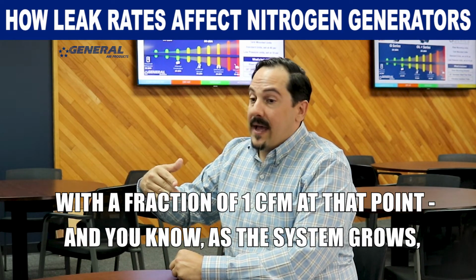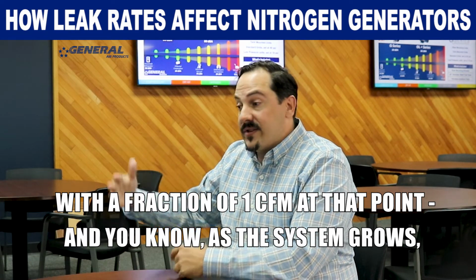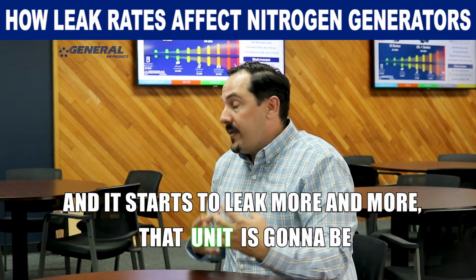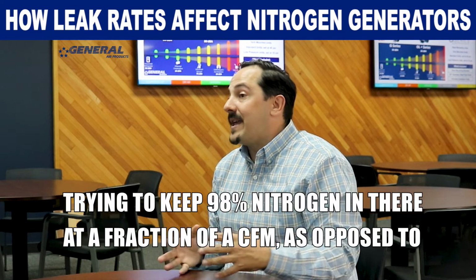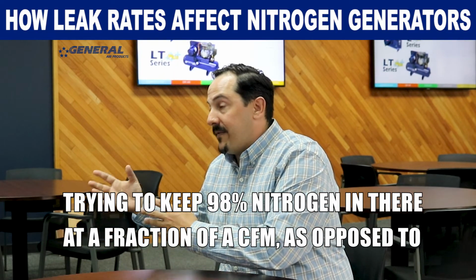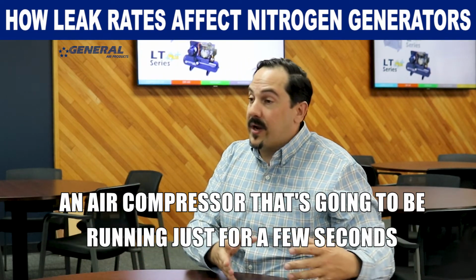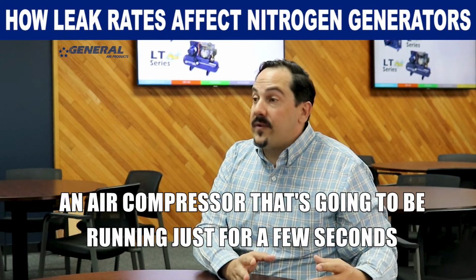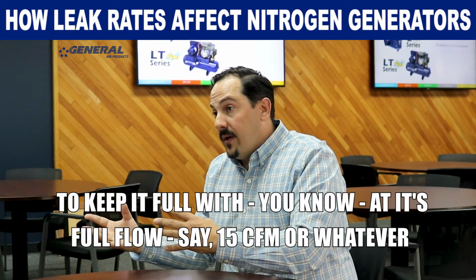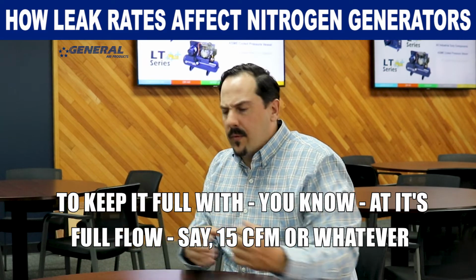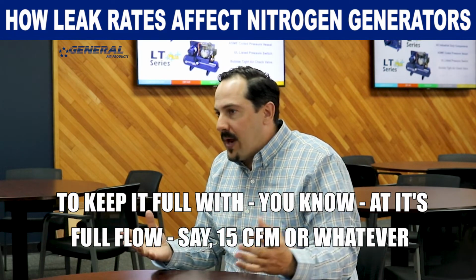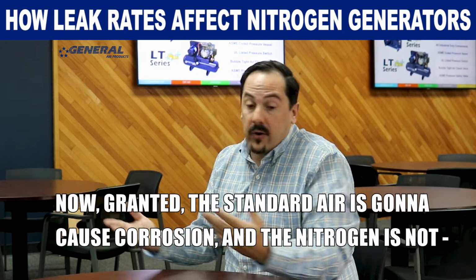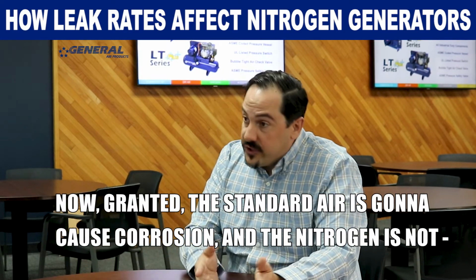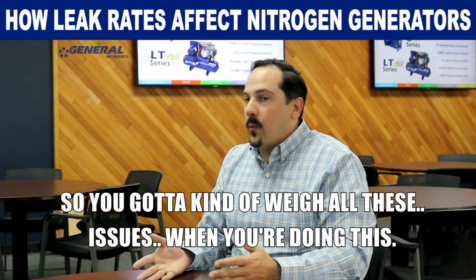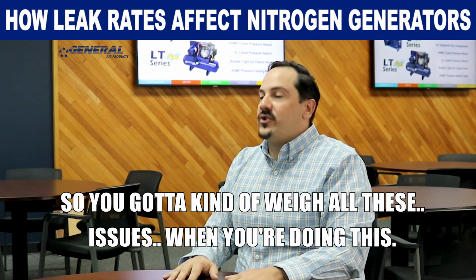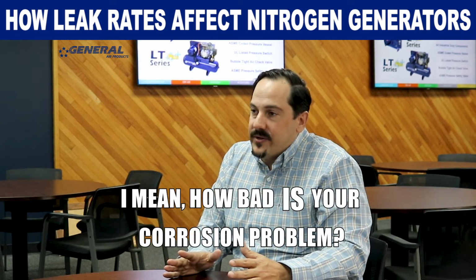and you're dealing with a fraction of 1 CFM at that point. As the system grows and starts to leak more and more, that unit is going to be running and running and running, trying to keep 98% nitrogen in there at a fraction of a CFM, as opposed to an air compressor that's going to run just for a few seconds to keep it full at its full flow, say 15 CFM or whatever, of just standard air. Now, granted, standard air is going to cause corrosion, the nitrogen is not. So you've got to weigh all these issues when you're doing this. How bad is your corrosion problem?